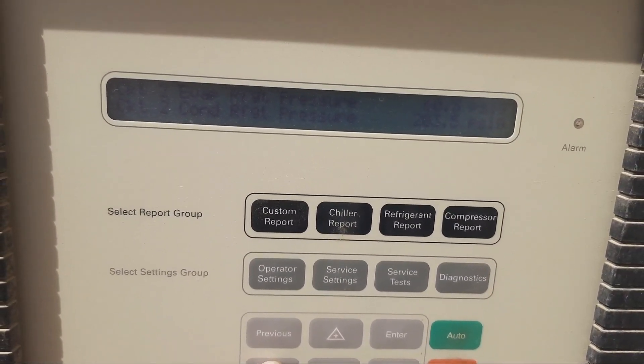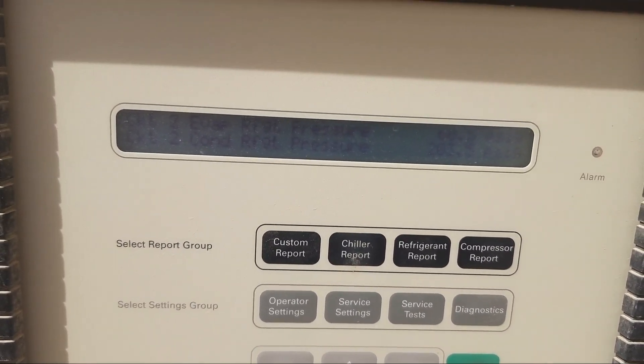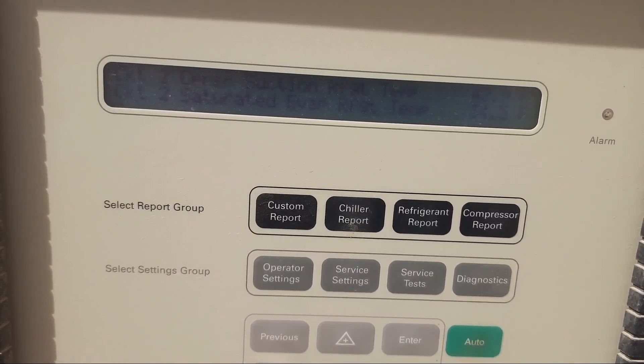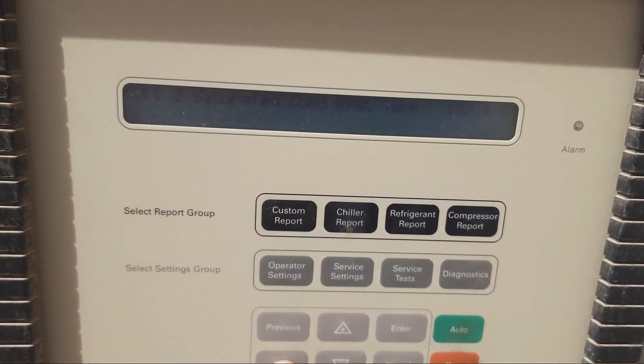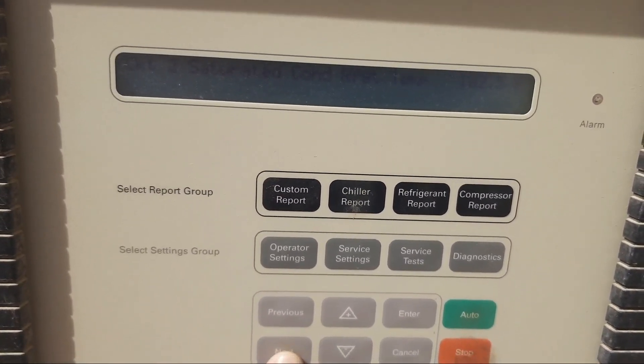For circuit two in running position: the suction pressure is 60 psi, the refrigerant condenser pressure is 203.5 psi, and the compressor suction refrigerant temperature is 42.9 degrees Fahrenheit. The evaporator temperature is 34.5 degrees Fahrenheit and the saturated condenser refrigerant temperature is 102.5 degrees Fahrenheit. This is all about the refrigerant report.